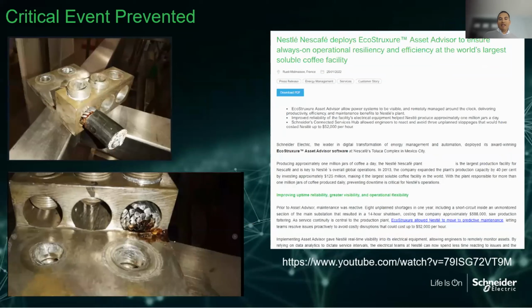When they disconnected the cable, you can see in the back end there's no damage — that's primarily where they shot their scan. But where the cable connects to the lug, the individual conductors were already starting to melt. This is what we detected with our sensor.